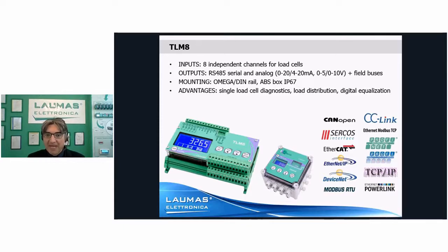It can be mounted rear panel on a DIN rail, or it can be put into an ABS box with an IP67 degree of protection. What are the main advantages? They come from the fact that in multi-channel devices, every channel is separately converted into digital by the microcontroller, and then the total weight is calculated by the device's firmware. This makes more information available with respect to traditional analog systems, and makes it possible to have single-channel diagnostics. So if there's a fault, you know immediately which load cell has generated it without making tests. You can have the load distribution display and digital equalization, but we will see all of these functions better in the videos.